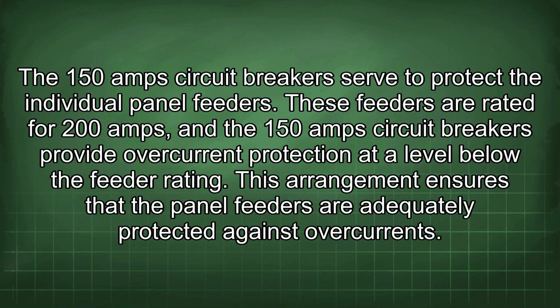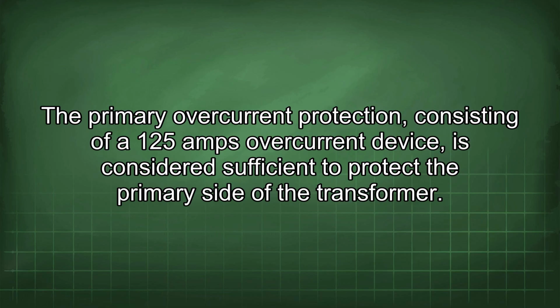The 150 amp circuit breakers serve to protect the individual panel feeders. These feeders are rated for 200 amps, and the 150 amp circuit breakers provide overcurrent protection at a level below the feeder rating. This arrangement ensures that the panel feeders are adequately protected against overcurrent.